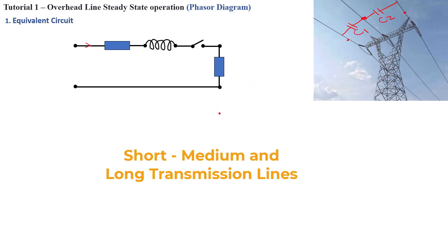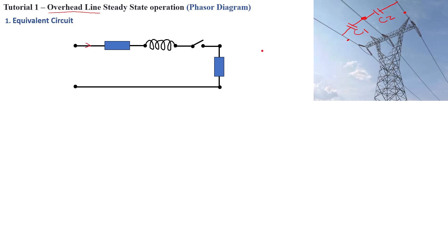What do we call a short transmission line? This is specifically important for voltage regulation. If you want to run a voltage regulation at the receiving end of the circuit, you have to take account of the capacitive current because that will create some voltage drop. But in a short transmission line, something around 10 to 15 kilometers, the capacitive current can be considered negligible for line regulation calculation. But if you are dealing with long to medium transmission line, you have to consider capacitive current.